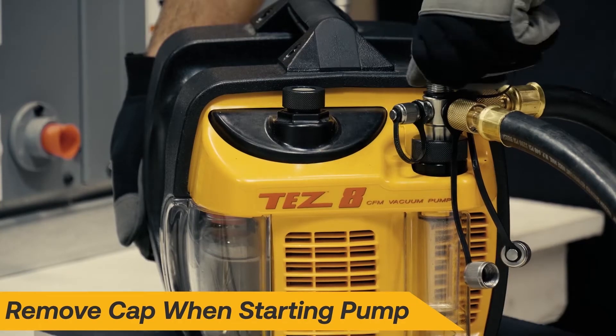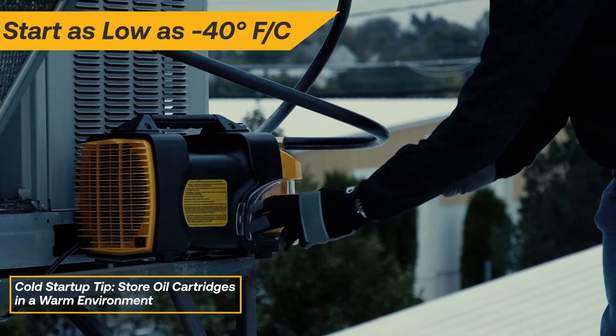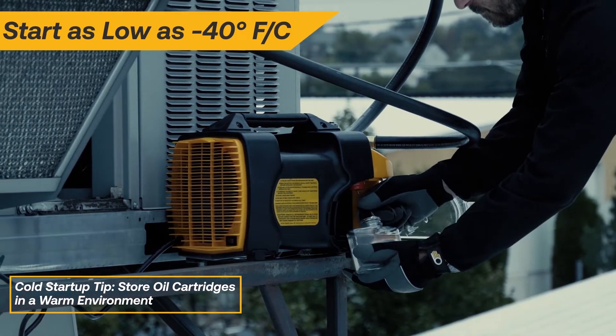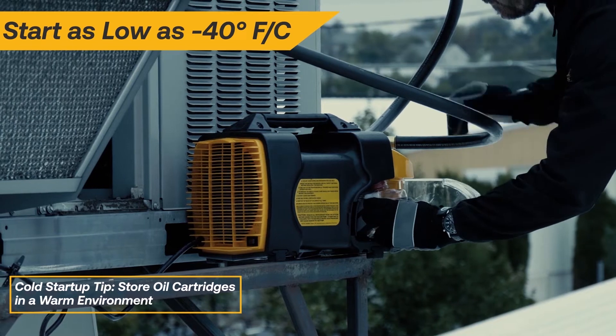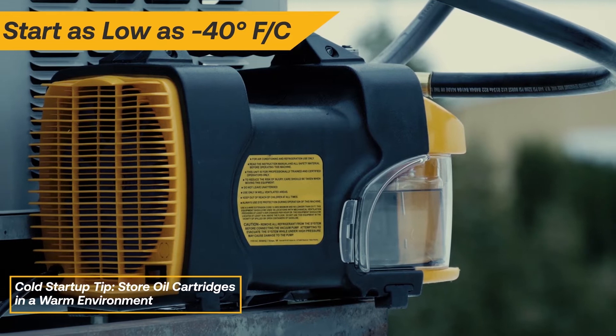Always start the pump with one of the caps off for trouble-free startup. The unique design of the TEZ-8 allows for easy startup in cold weather. Keep the oil cartridges stored in a warm environment and install them when you're ready to begin evacuation.